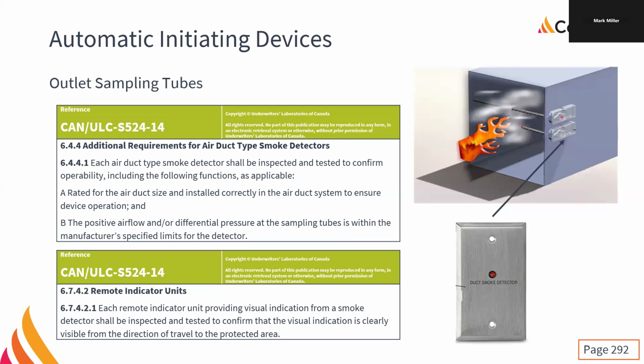We're going to know that from zoning, right? Air handling unit number 1 is going to have its own zone. The duct smokes on air handling unit 1 are going to have their own zone on the panel. Nice and easy if you have one duct smoke on air handling unit 1. But if you end up having 4 or 8 or 12 or 20, well, which one is it? We're going to want to be able to find that remote LED so that we can figure out which device has gone into alarm.